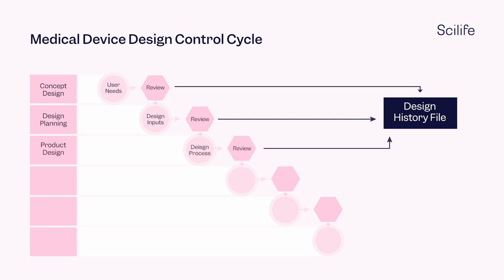The next step in establishing design control is to oversee the design input. The design input of a device is primarily the design requirements. Design requirements are criteria defining the function, user requirements, and features that allow the designers to create a functioning device design from an idea. During this stage, the basic guidelines based on which a device will be made are created.